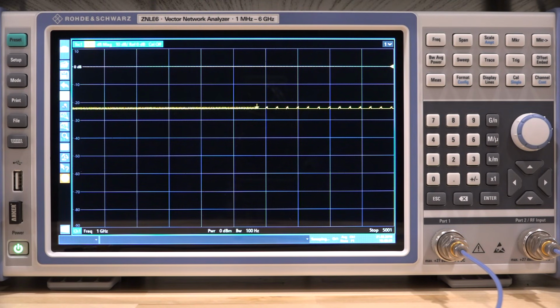It'd be nice if it had a mechanical attenuator also, but you can use an external attenuator if you need it. Normally, a range that I think is very nice for network analyzers is between +10, let's say, to -20. Between +10 and -20 is a good range. But again, this is an entry-level instrument, so some compromises have to be made.